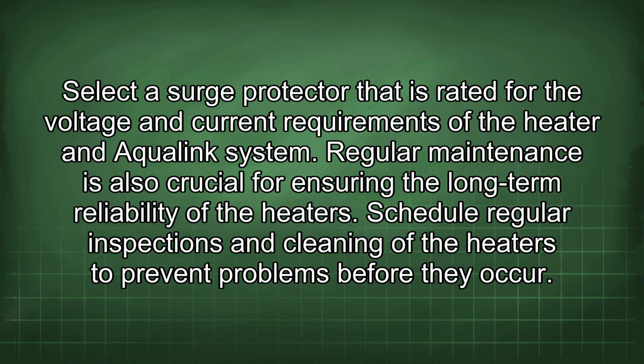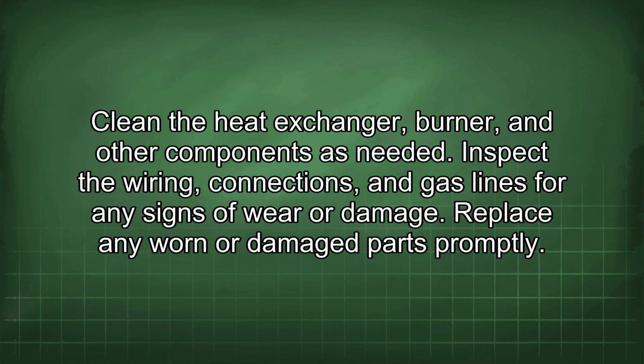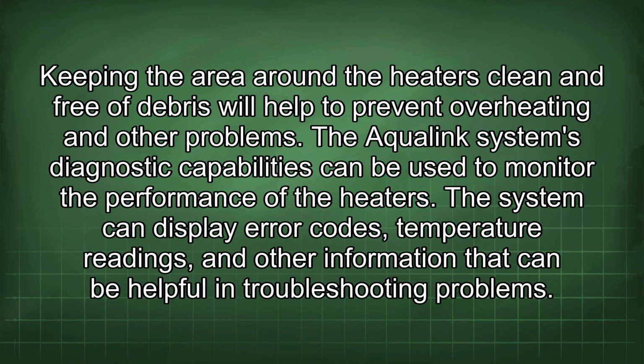Regular maintenance is also crucial for ensuring the long-term reliability of the heaters. Schedule regular inspections and cleaning of the heaters to prevent problems before they occur. Clean the heat exchanger, burner, and other components as needed. Inspect the wiring, connections, and gas lines for any signs of wear or damage. Replace any worn or damaged parts promptly. Keeping the area around the heaters clean and free of debris will help to prevent overheating and other problems.